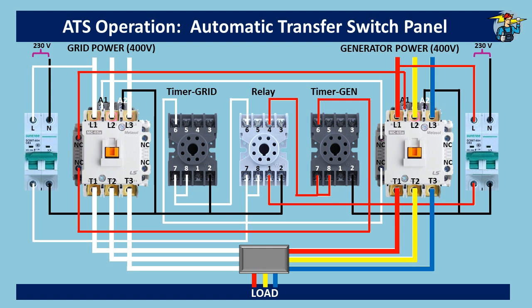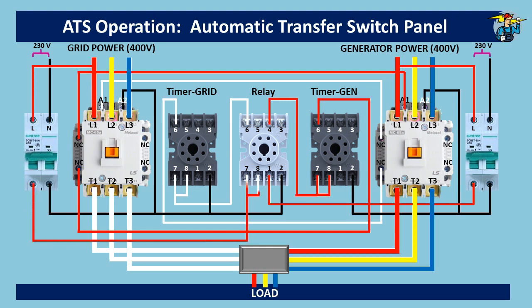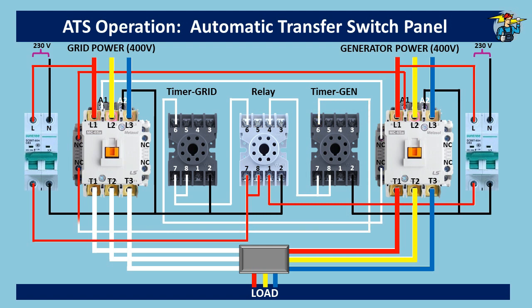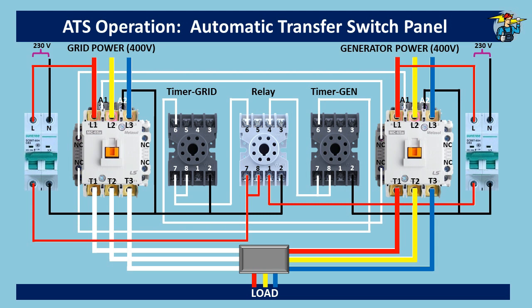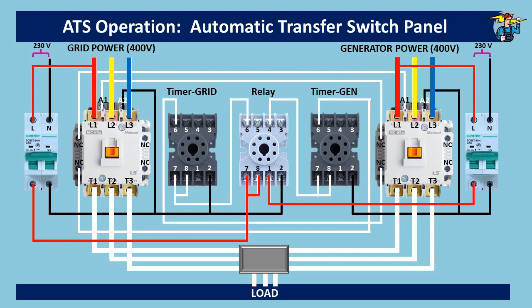The load runs on generator power until grid power is restored. When grid power comes back, the relay gets power through port 7, and the normally closed connection between ports 1 and 4 opens up. This stops power to the generator timer. With the generator timer de-energized, A1 of the generator contactor does not get power, stopping generator power to the load.